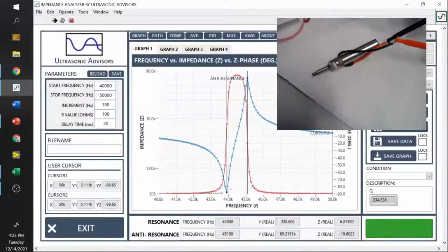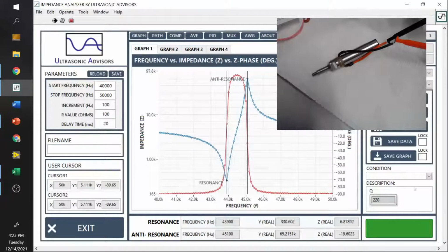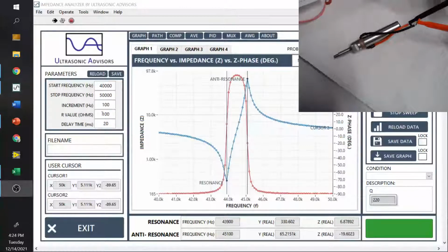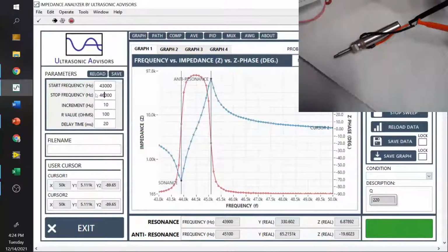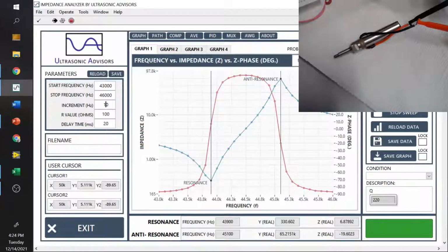Okay, so that's our transducer. We don't see very many points around the resonance frequency from which we're going to be calculating. Let's just run a Q measurement right now. That gets us to 220. I want you to notice what happens when I increase the number of points. This is a really big issue, not having sufficient points in your analysis. So we're going to be running 10, and I do want to get a little bit closer so it doesn't take forever, so let's go from 43 to 46 kilohertz. This is the bare transducer, as you see in the picture, and let's run that again.